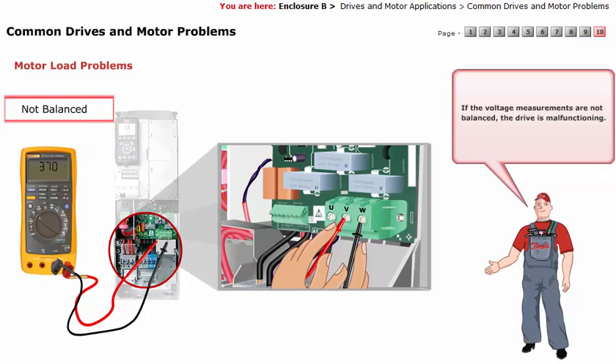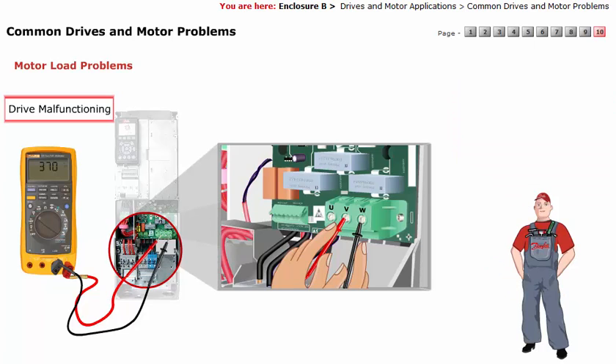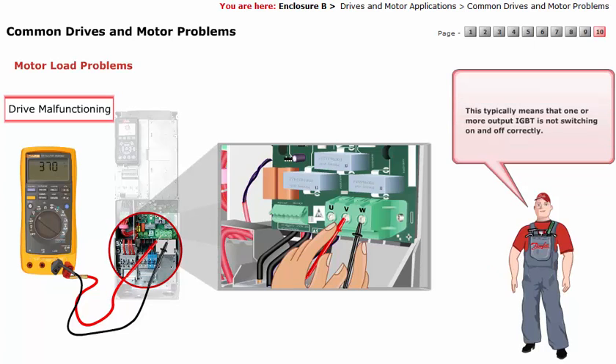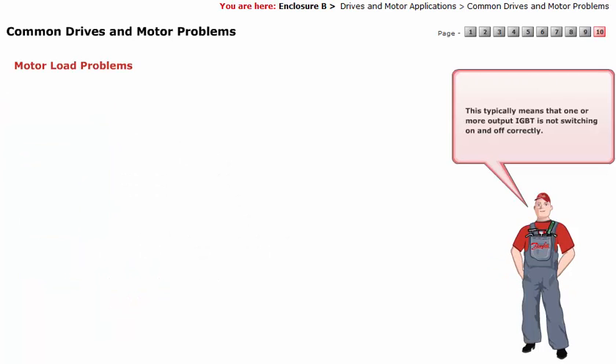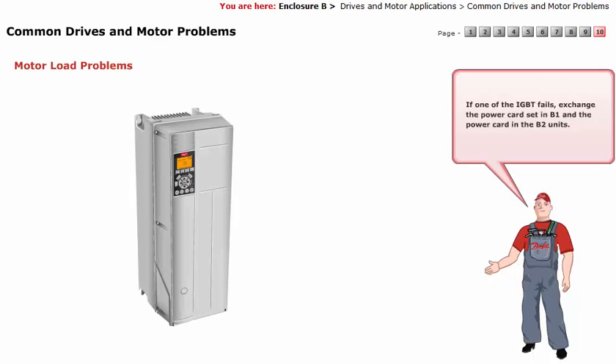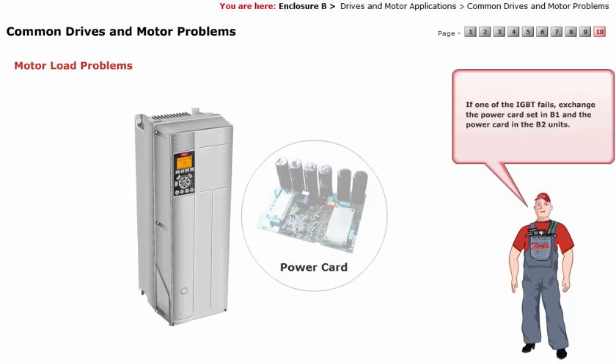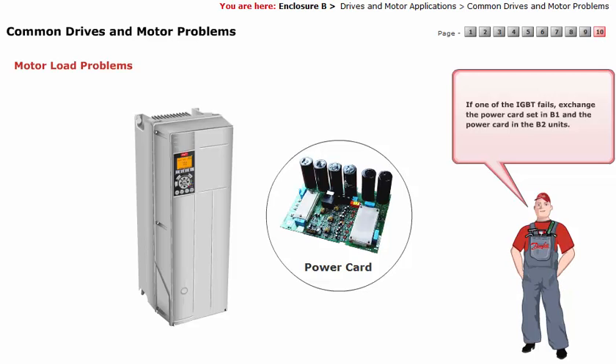If the voltage measurements are not balanced, the drive is malfunctioning. This typically means that one or more output IGBTs are not switching on and off correctly. If one of the IGBTs fails, exchange the power card set in B1 units and the power card in the B2 units.